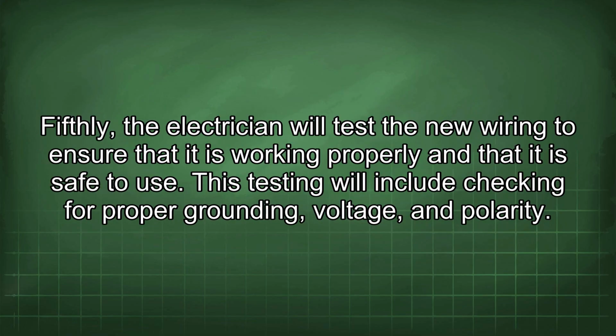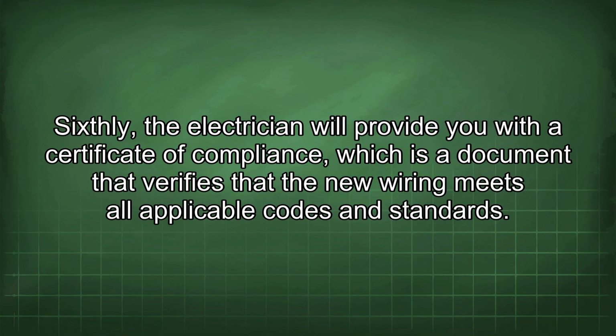Fifthly, the electrician will test the new wiring to ensure that it is working properly and that it is safe to use. This testing will include checking for proper grounding, voltage, and polarity. Sixthly, the electrician will provide you with a certificate of compliance, which is a document that verifies that the new wiring meets all applicable codes and standards.